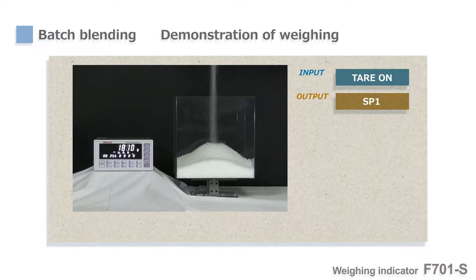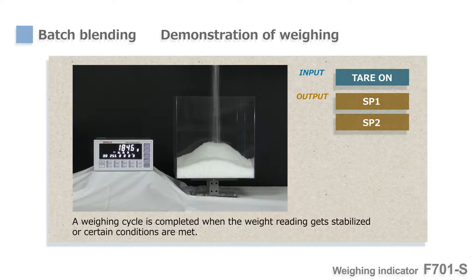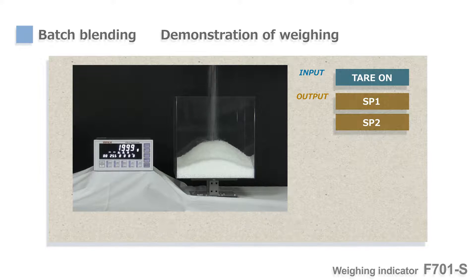Yet, as the weight level reaches the targets, F701S sends SP1 and SP2 signals to control the gate and reduce the dosing amount gradually. Then, right before the weight reaches SP3, the gate is closed completely.